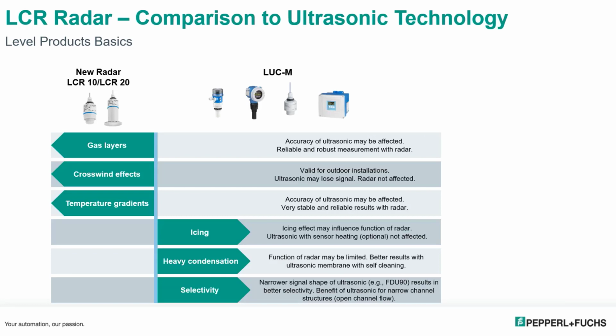Because the freestanding radar is so similar to the ultrasonics, we have a comparison chart here for when to use one or the other. For gas layers, because of the high frequency of the freestanding radar, it will penetrate that better than the ultrasonics, giving you a much better signal back to the radar system. Crosswinds, you could lose in outside applications. The wind can make you lose your signal from the ultrasonic, whereas the high frequency will penetrate that. Temperature gradients, even though the ultrasonic has temperature compensation, that handles changes in the temperature. With temperature gradients, we don't know what the temperature is far away from the probe, so these will affect the accuracy of the ultrasonic, but not the freestanding radar. Icing and heavy condensation, you're better off with the ultrasonic sensors.